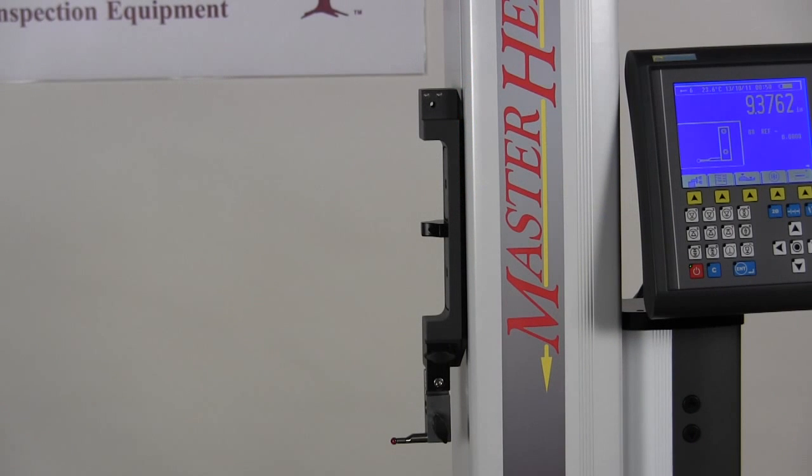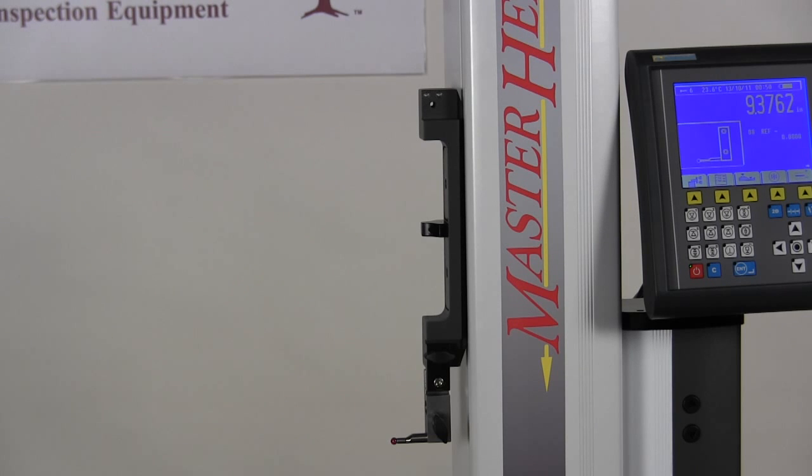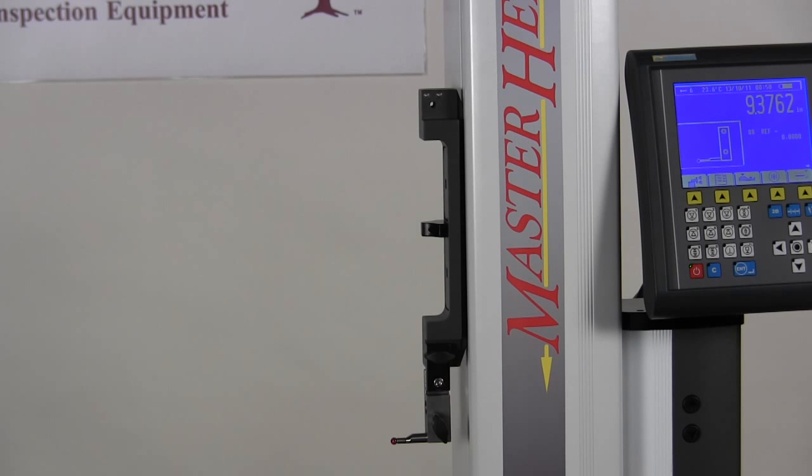The MH600 features a measuring range of 0 to 600 millimeters or you can flip the probe to its alternate position and gain an additional 350 millimeters of range. The unit comes standard with a 6 millimeter Ruby probe with other probes available as an option.